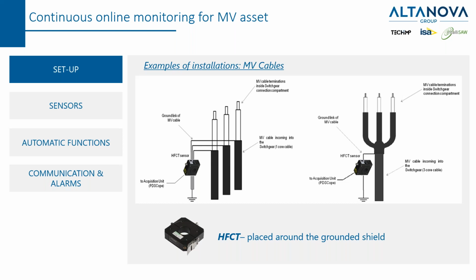It could be placed around the grounded shield in 2 different layouts. For example, if we have the 3 single core cable, the 3 ground connections could be used inside the same sensor, or even if there is a 3 core cable, use the 1 ground connection in 1 single HFCT. There are some layouts, where available, that require 3 sensors for the 3 single core cables, 1 for each ground link connection. This allows the user to identify which cable has more amplitude of PD and recognize immediately which one is affected by the partial discharge.